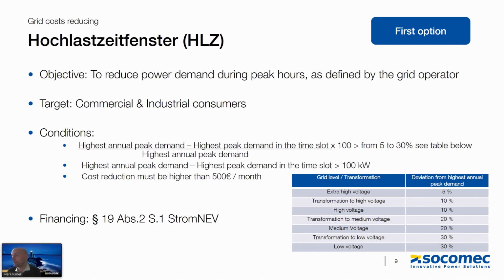So for example, it could be between 4 and 5 p.m. in the afternoon when the demand on the grid is high. We then divide that by our highest annual peak demand and multiply it by 100. This will give us a percentage, and you can see from the table here the eligibility criteria. So if we are looking at a low voltage installation, your deviation must be at least 30%. When we look at our highest annual peak minus our highest peak demand in the time slot, it must be greater than 100 kilowatts, and the cost reduction must be higher than 500 euros per month.